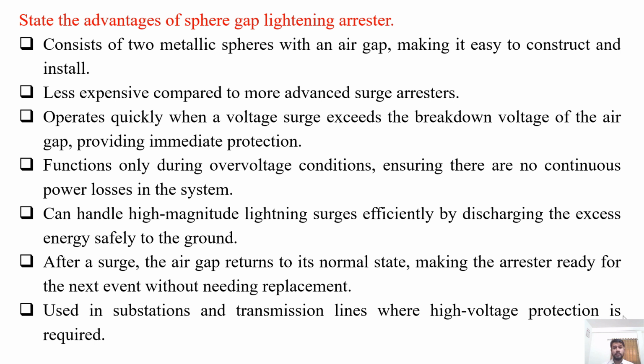So there are several advantages of this kind of lightning arrestor, but some of them are listed over here. Consists of two metallic spheres with an air gap, making it easy to construct and install. Less expensive compared to more advanced surge arrestors. Operates quickly when a voltage surge exceeds the breakdown voltage of the air gap, providing immediate protection. Functions only during overvoltage or surge conditions, ensuring there is no continuous power loss in the system. It can handle high magnitude lightning surges efficiently by discharging the excess energy safely to the ground.